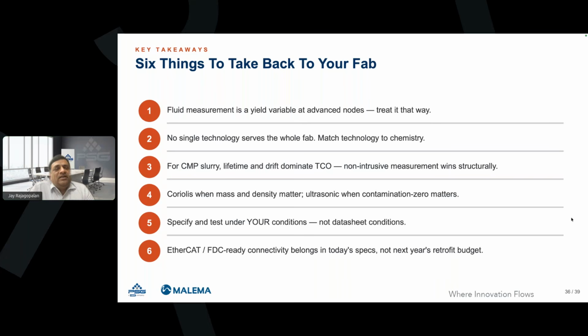And obviously non-intrusive measurement wins in some applications, but not in all cases. Coriolis, as I told you, mass and density matters. Ultrasonic, when contamination free, matters. Specify and test under your condition. So if you're an OEM or end user, the test data for your actual application is more critical than just data sheet conditions. That is very important.